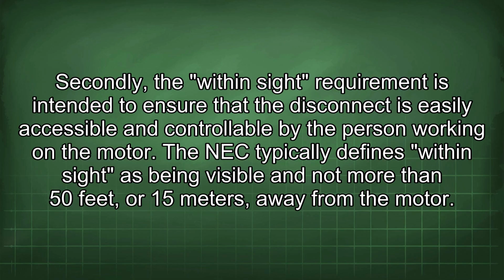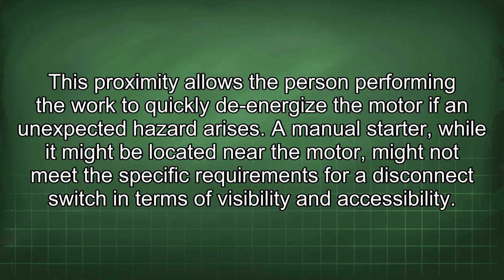Secondly, the within sight requirement is intended to ensure that the disconnect is easily accessible and controllable by the person working on the motor. The NEC typically defines within sight as being visible and not more than 50 feet or 15 meters away from the motor. This proximity allows the person performing the work to quickly de-energize the motor if an unexpected hazard arises. A manual starter, while it might be located near the motor, might not meet the specific requirements for a disconnect switch in terms of visibility and accessibility.